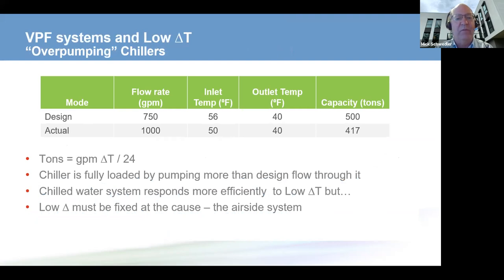How about in a variable primary flow system? This was really brought up first, I'll say in the 1990s, by Gil Avery. He referred to it as overpumping chillers. In a VPF system, if we have manifolded the pumps, we're not confined to staying at the design flow rate. Remember, the chillers have the design flow rate, they have the minimum flow rate, and then they have the maximum flow rate. We can go anywhere from the design all the way up to the maximum flow rate. As long as we don't go above that, we're fine.